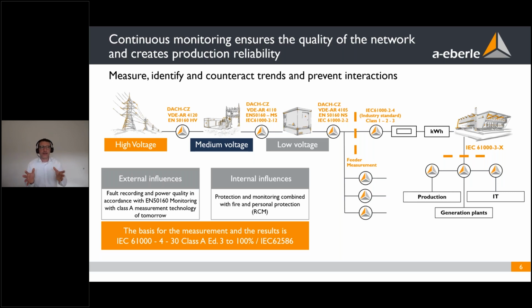And what do all these standards have? You have to know how measures are calculated, because if you don't exactly describe the calculation methods, if you don't exactly describe how the power quality is measured and how the measures are calculated, it doesn't help you. Because if there are thresholds, the thresholds must be calculated with the same technology. And these calculation methods are described in one product standard, IEC 62586, which exactly describes how measurement technology must be produced.